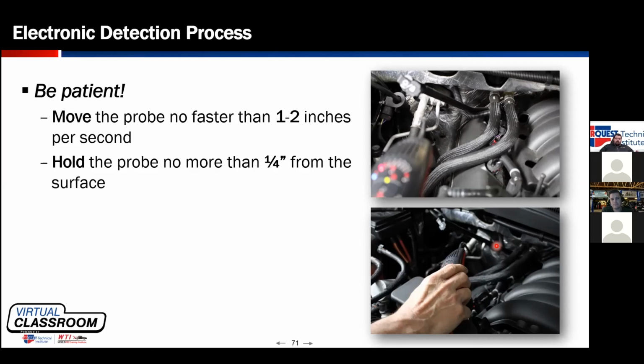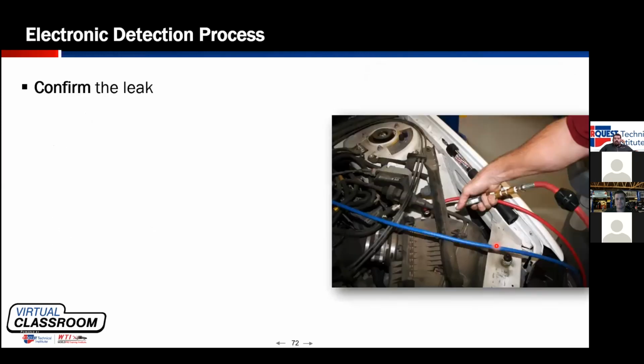The SAE standard for J2791, J2913 is that the detector can be at 3/8 of an inch. Closer is better without touching. I generally do like to be within 1/4 of an inch. And you generally want to check both the top and the bottom. Refrigerant is heavier than air, so it will tend to fall to the bottom of the fitting that is leaking, or to the bottom of the leak. The opposite of that, if you are using forming gas for leak detection, the hydrogen in forming gas is lighter than air, so your leak will tend to be at the top of the component.